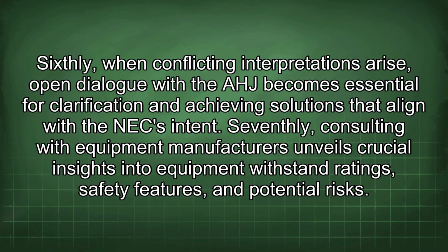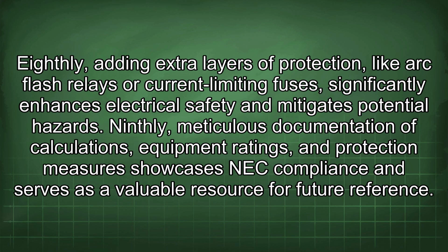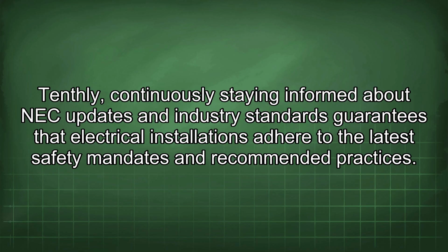Seventhly, consulting with equipment manufacturers unveils crucial insights into equipment withstand ratings, safety features, and potential risks. Eighthly, adding extra layers of protection, like arc flash relays or current limiting fuses, significantly enhances electrical safety and mitigates potential hazards. Ninthly, meticulous documentation of calculations, equipment ratings, and protection measures showcases NEC compliance and serves as a valuable resource for future reference. Tenthly, continuously staying informed about NEC updates and industry standards guarantees that electrical installations adhere to the latest safety mandates and recommended practices.